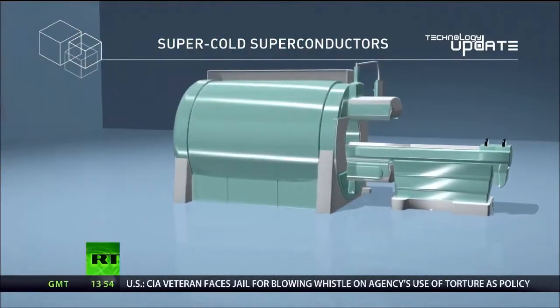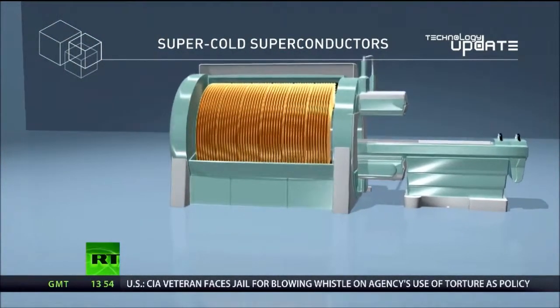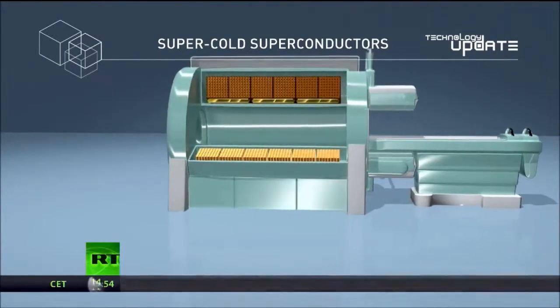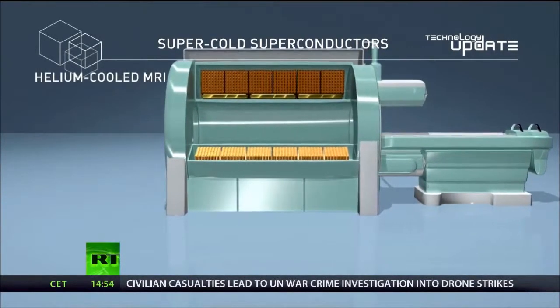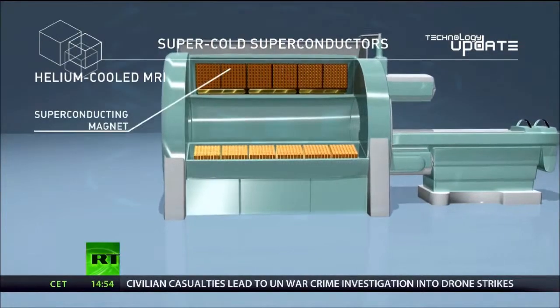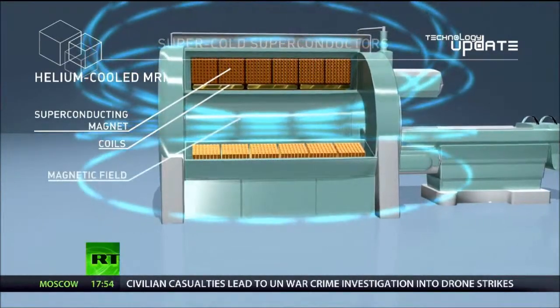Now, traditional MRI scanners look like this, with a table for the patient jutting out from the borehole. But the real heart is a superconducting magnet around that human-sized hole. This generates the stable magnetic field that makes the whole imaging process possible. And closer to the center lies gradient and radio frequency coils.